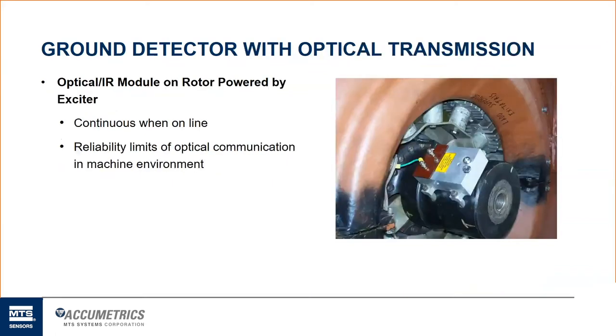So the next style of ground fault detector is an optical transmission. This is just an optical IR module that mounts out on the rotating shaft. It gets its power source from the excitation of the field voltage itself. So it is continuous as long as the machine is online and running. It does have some reliability limits, of course, for optical communication in a machine environment. If it's in a coal plant, a dirty or dusty environment, those lenses can get corroded or covered up, and it obviously stops working if that happens.